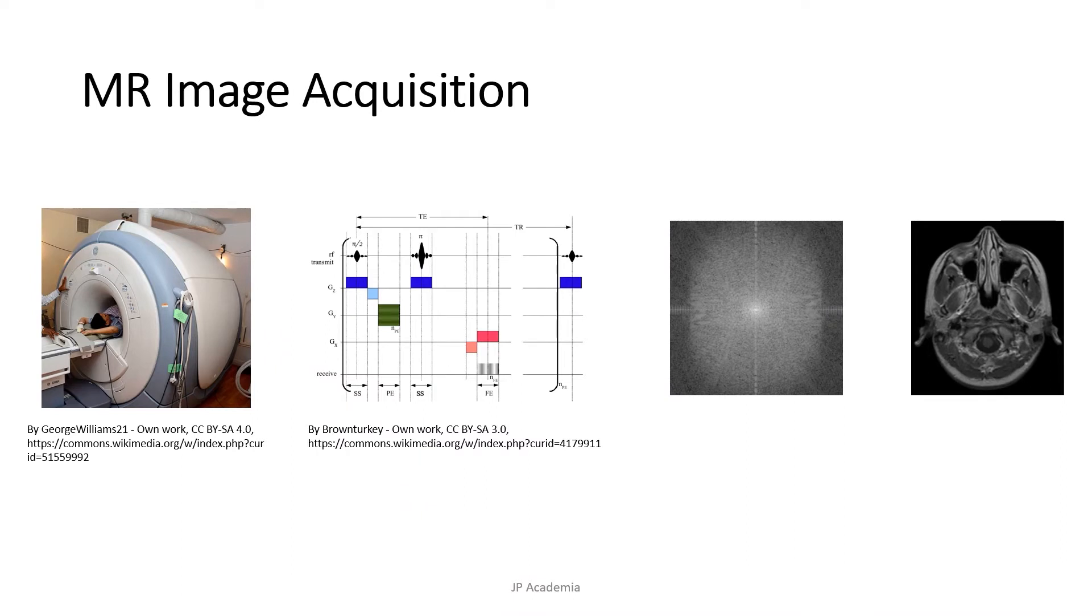Generally, this is how we acquire image in magnetic resonance imaging. The patient will enter the machine, this cylindrical thing. Then an MR pulse sequence is chosen, which is just a programmed set of changing magnetic gradients. We have here along the X, along the Y, and along the Z. Each sequence will have a number of parameters and multiple sequences grouped together into an MR protocol.